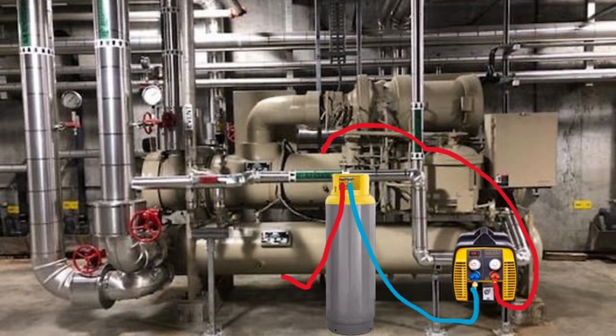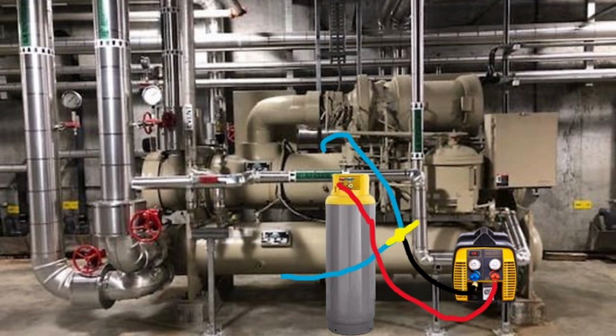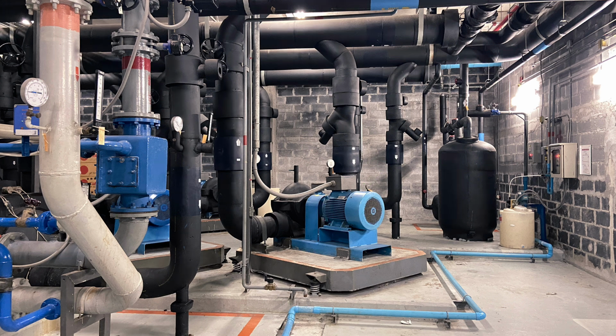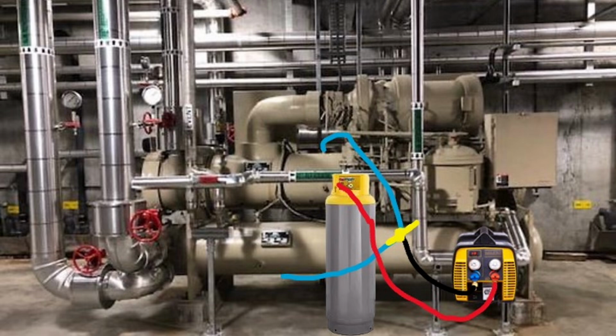You can check your progress with the use of the sight glass on the hose from the condenser to the liquid port on your tank. Once all of the liquid is out of the sight glass for 10 minutes, and only vapor is left, reconfigure your hoses, and switch over to vapor recovery like you would on any other AC unit. Be sure that all of your pumps are running during this step, and keep going until the whole machine hits 40 degrees saturated on your PT chart. If you're working with 134A, that's around 35 psi.